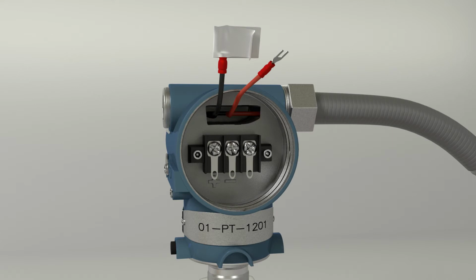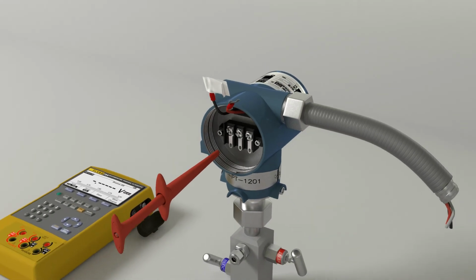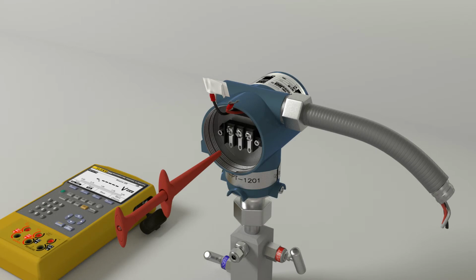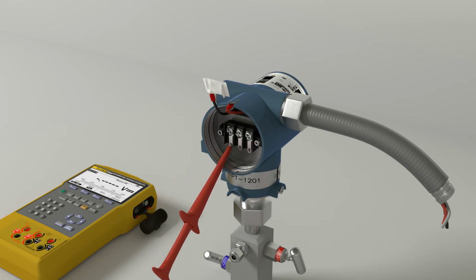Take your red Fluke test terminal connector and connect it to the test terminal. The connector is spring-loaded, and if you pull back on the forward part of the connector, it will expose the connection point. The test terminal is the little piece of metal attached to the termination in the transmitter. Pull the forward plastic back and hook the connector to the test terminal. Then do the same thing for the negative with the black connector.